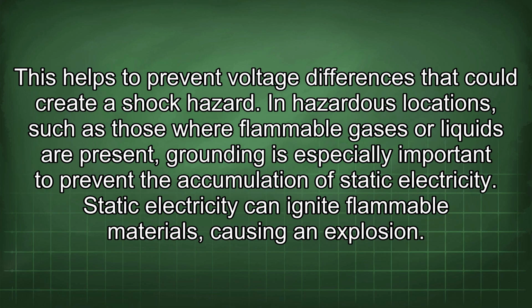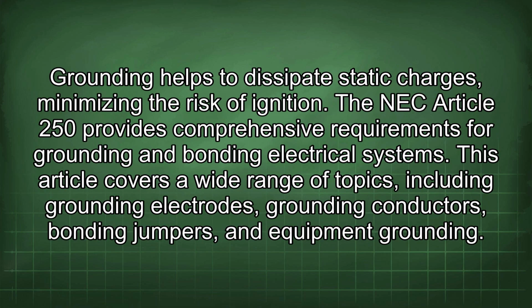In hazardous locations, such as those where flammable gases or liquids are present, grounding is especially important to prevent the accumulation of static electricity. Static electricity can ignite flammable materials, causing an explosion. Grounding helps to dissipate static charges, minimizing the risk of ignition.